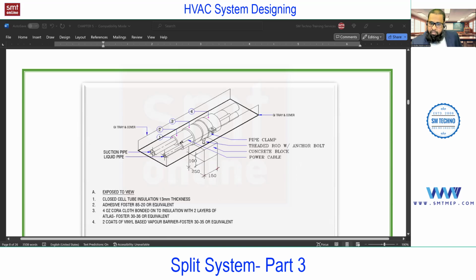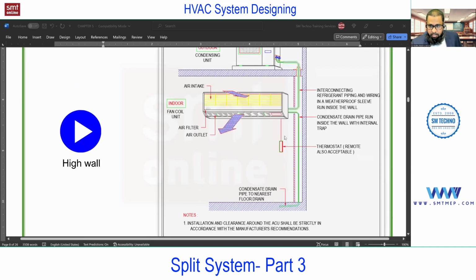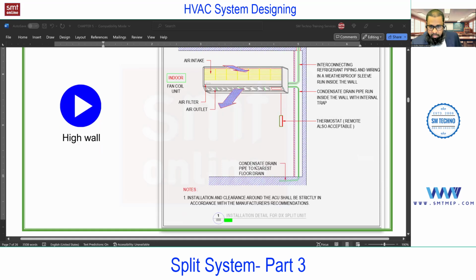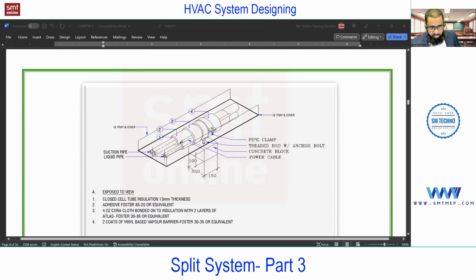Next, this is a detailed drawing for the pipe. You see, this pipe is connected from indoor to outdoor. No? Here is a section. You see, the bigger is a suction line, the smaller is a liquid line, and both are insulated separately.